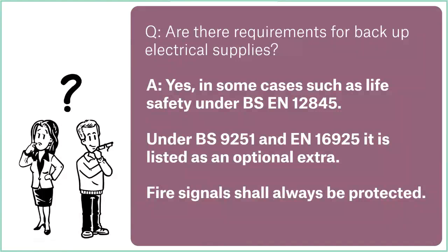If you're using 2 electric pumps, then again, you don't necessarily need electrical backup supplies as long as you can take the electric from 2 different sources. So 2 different substations, I guess, it's not my area. But yeah, if you can say 1 failure of main supply isn't going to knock out both pumps, then you can do it that way. But if they're both coming from the same supply, then yes, you would need generators, switch panels, etc., to make sure that 1 electrical failure is not going to knock out both pumps.